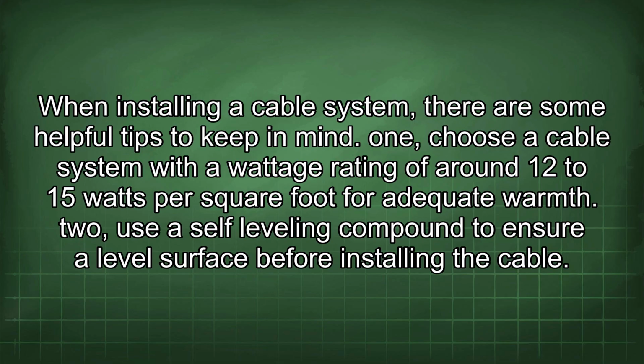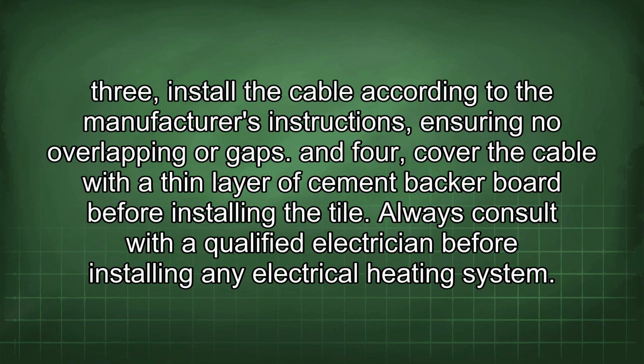1. Choose a cable system with a wattage rating of around 12 to 15 watts per square foot for adequate warmth. 2. Use a self-leveling compound to ensure a level surface before installing the cable. 3. Install the cable according to the manufacturer's instructions, ensuring no overlapping or gaps. And 4. Cover the cable with a thin layer of cement backer board before installing the tile. Always consult with a qualified electrician before installing any electrical heating system.